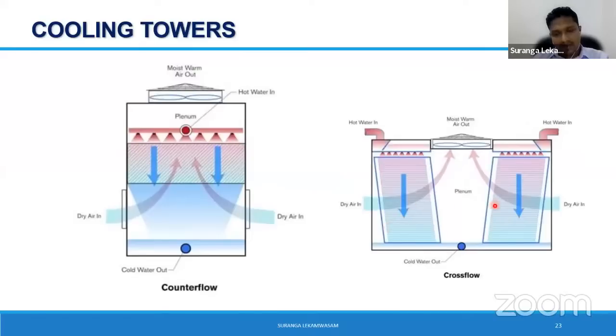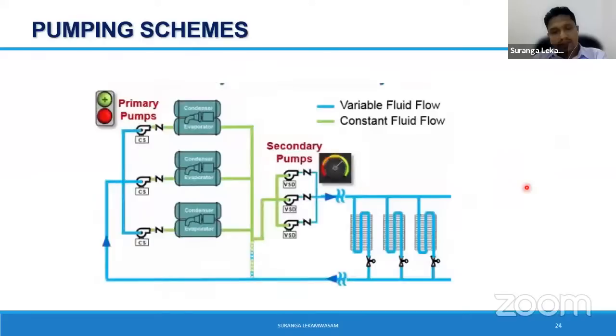But the problem with cross flow is that, just by seeing, your infill is only at the periphery of the cooling tower. So you need to have a bigger tower. Footprint is bigger, but efficient. Nowadays, I can see many people installing cross flow cooling towers. So with that, I land onto the pumping schemes, which is again something very important.